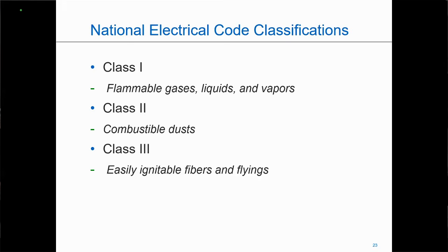In a combustible dust area, it's not uncommon to have a primary explosion, the initial explosion. And when that initial explosion happens, it shakes the building, and dust that had settled now becomes airborne. And that dust in suspension will ignite. Secondary explosion. And sometimes you can have a series of secondary explosions. And then Class 3 is your easily ignitable fibers and flyings, cottons, rayons. These particular substances aren't quite as likely to be airborne. So in this particular case, it's often a flash fire, but they all can be very dangerous and they all can create injury and kill.